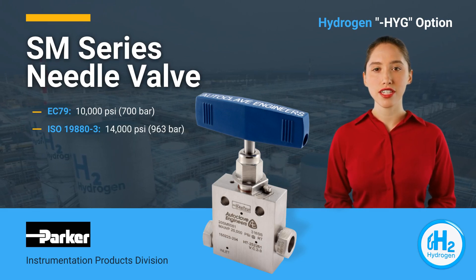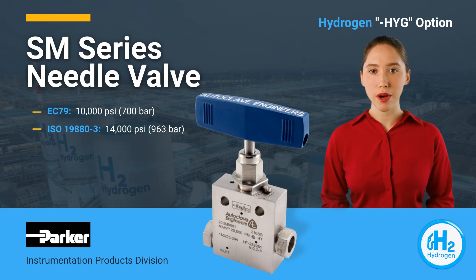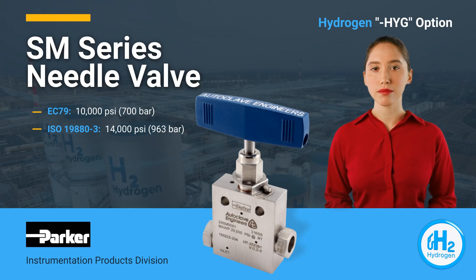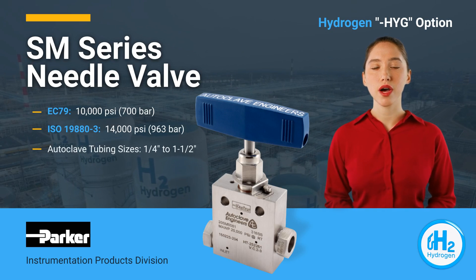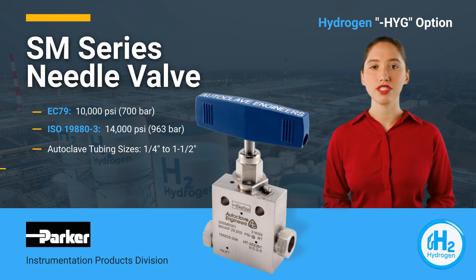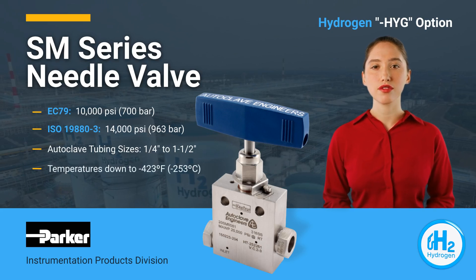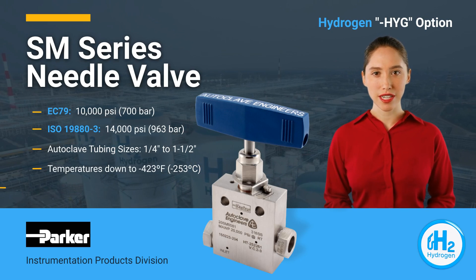Designed for even higher pressures of up to 20,000 PSI using the Parker Autoclave Engineers Medium Pressure Cone and Thread Connection, these valves are available in sizes from a quarter inch to one and a half inches and can be used on both gaseous and liquid hydrogen applications, down to minus 423 degrees Fahrenheit or minus 253 degrees Celsius.